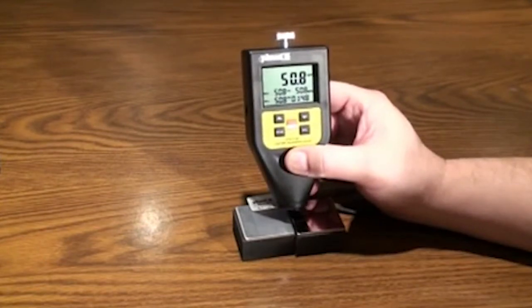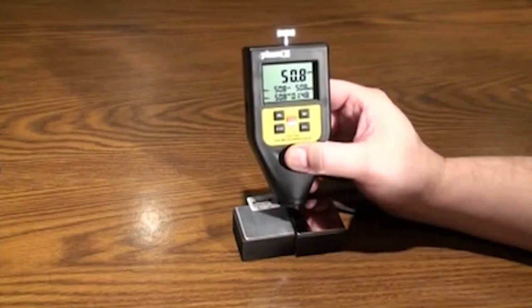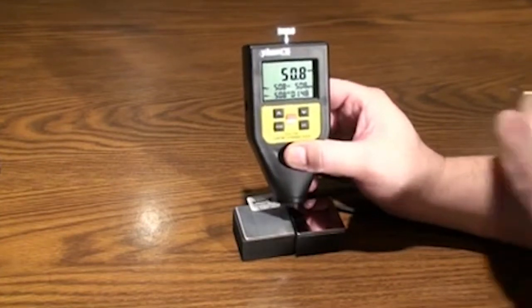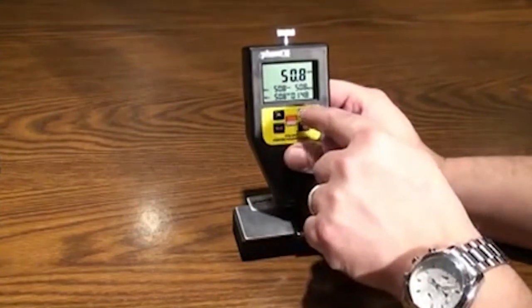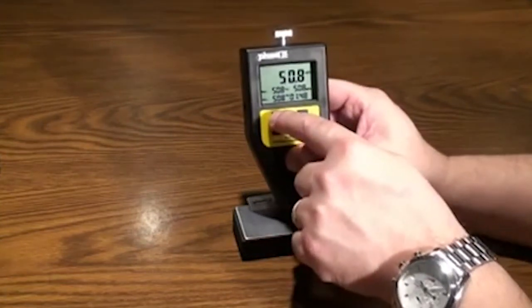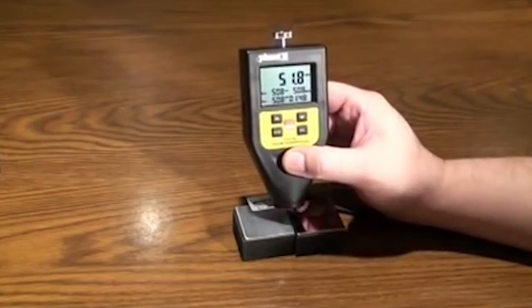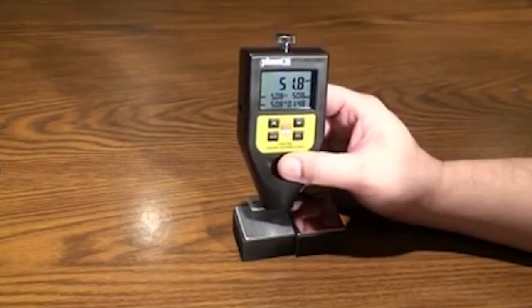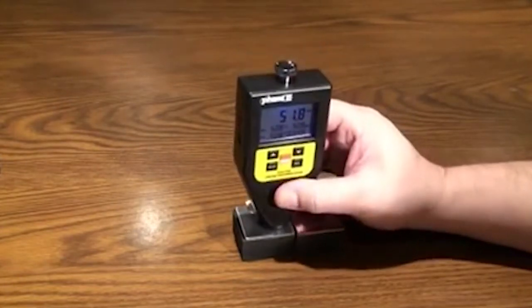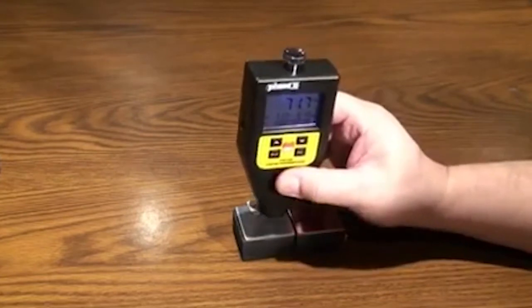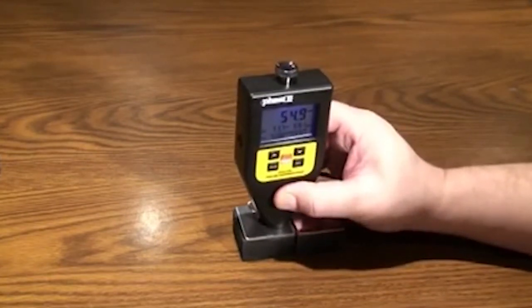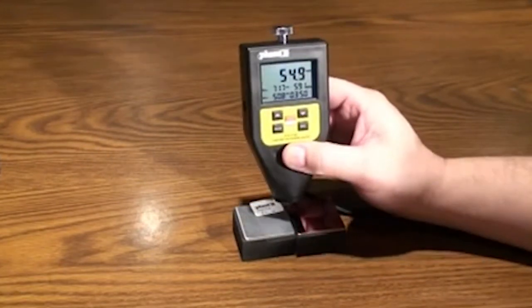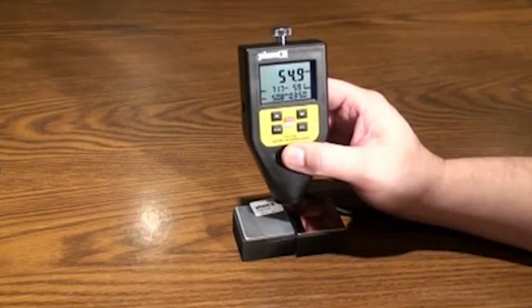Should you find that your readings are not within acceptable tolerances, take a test and after removing the probe from contact, use the arrow buttons to calibrate to the known value of the calibration standards. Then repeat test taking procedure. Repeat this step until result is correct. Note this model on screen displays minimum, maximum readings, average, and number of stored values.